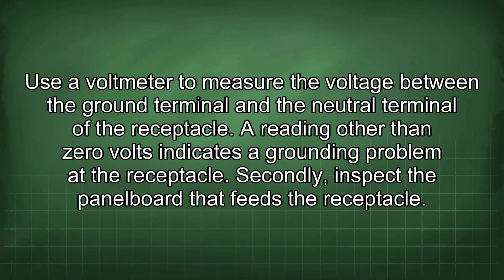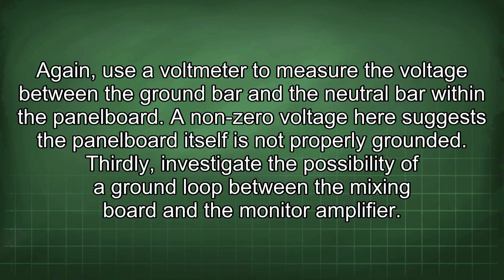Secondly, inspect the panel board that feeds the receptacle. Again, use a voltmeter to measure the voltage between the ground bar and the neutral bar within the panel board. A non-zero voltage here suggests the panel board itself is not properly grounded.